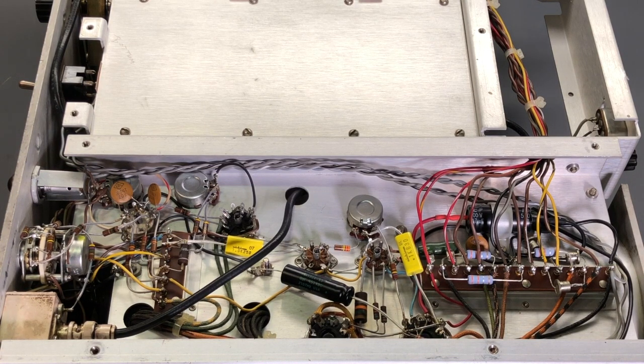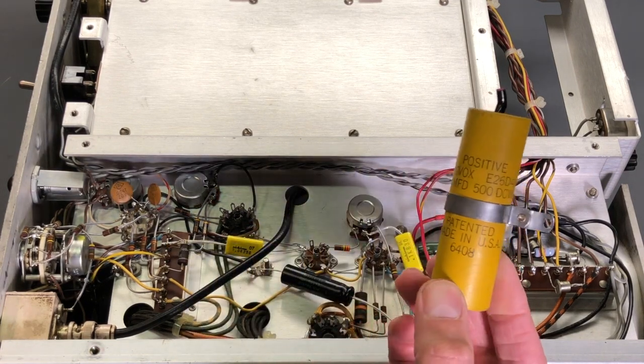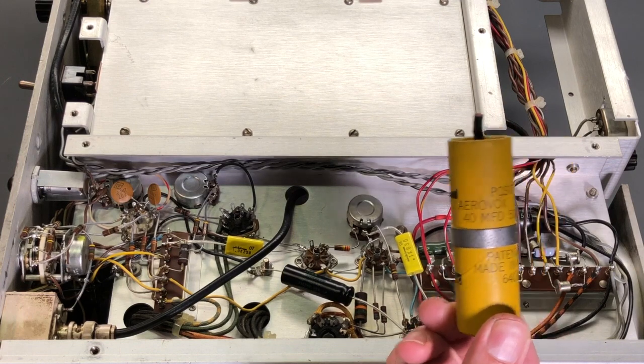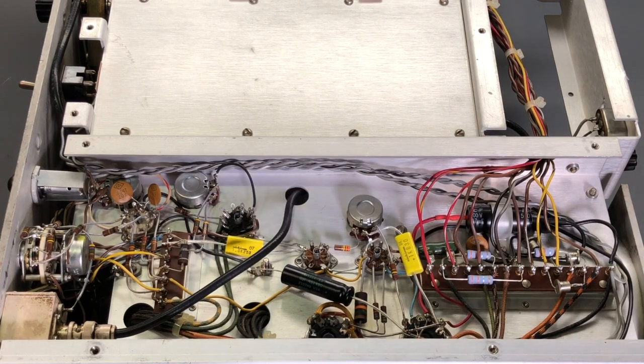So when replacing capacitors, it's perfectly fine to increase the capacitance if necessary. You could also lower the capacitance slightly. Sometimes on these old components like this capacitor, a 40 microfarad 500 volt was just not a common value, but a 47 microfarad is a common value now, so perfectly fine to increase that capacitance slightly. But with capacitors, you never want to replace it with a lower voltage rating, so you always need to go equal or higher in the voltage rating. Of course, within reason. I mean, you wouldn't go in here and put a 1,000-volt capacitor or something like that. But again, within reason, increasing it slightly is perfectly fine.